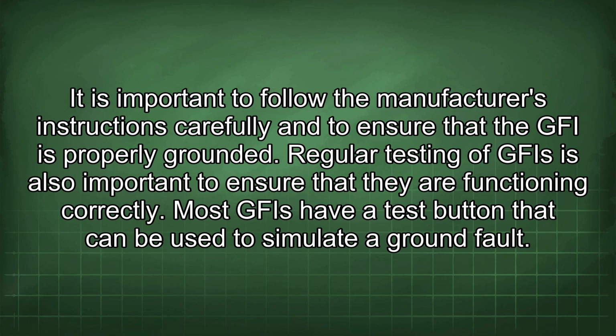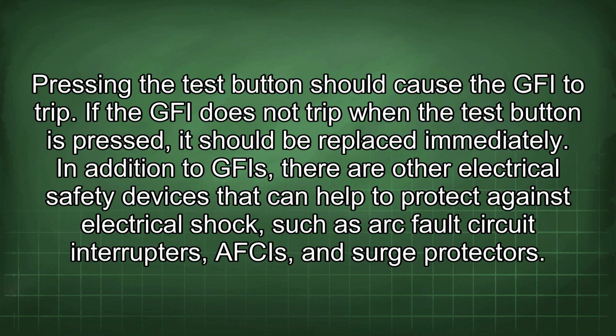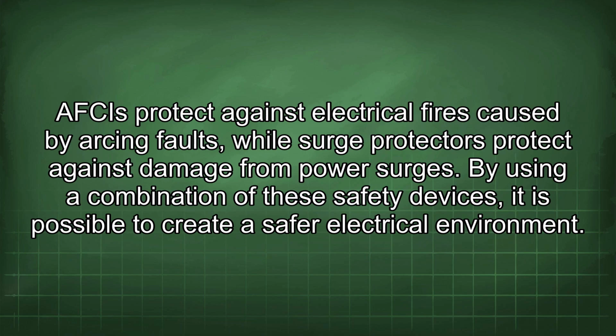Regular testing of GFI is also important to ensure that they are functioning correctly. Most GFI have a test button that can be used to simulate a ground fault. Pressing the test button should cause the GFI to trip. If the GFI does not trip when the test button is pressed, it should be replaced immediately. In addition to GFI, there are other electrical safety devices that can help to protect against electrical shock, such as arc fault circuit interrupters, AFCIs, and surge protectors. AFCIs protect against electrical fires caused by arcing faults, while surge protectors protect against damage from power surges. By using a combination of these safety devices, it is possible to create a safer electrical environment.